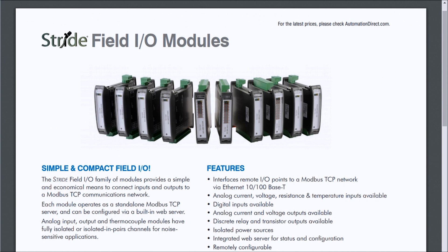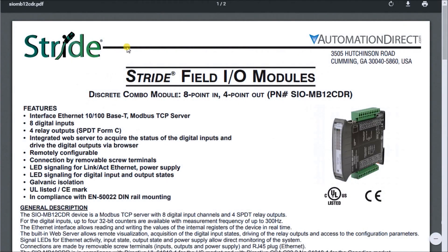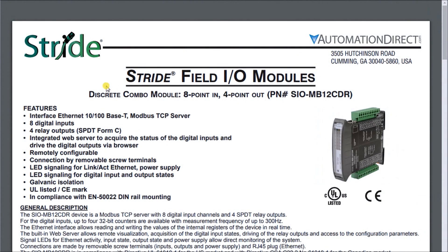On screen here is a general overview for the Stride Field I/O, and then we have our two modules. The first one is our discrete combo module, which has eight inputs and four outputs. It interfaces using the Ethernet Modbus TCP server. We have eight digital inputs and four relay outputs which are single pole double throw, so we have a normally open and normally closed contact on those outputs. There's an integrated web server used to acquire status and configure the module, plus LEDs for indication.